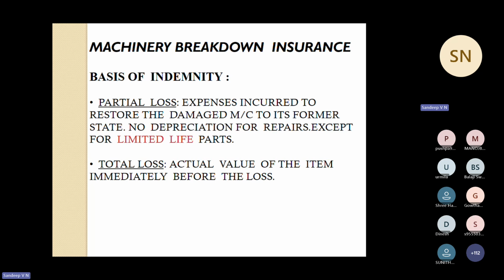For example, a bearing is a continuously wearing part. Another example is the old picture tube, the CRT tube, or the X-ray tube of an X-ray machine. These all have limited life. In some machines, the manufacturer himself will specify the life of the part, and after that life, you have to change it.